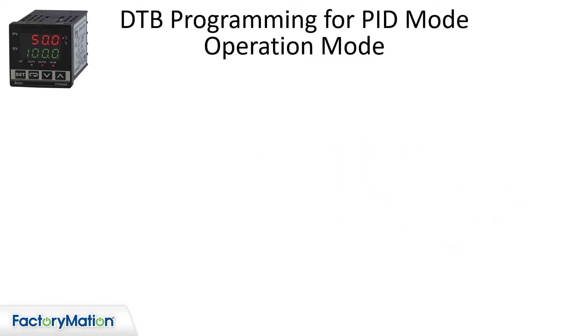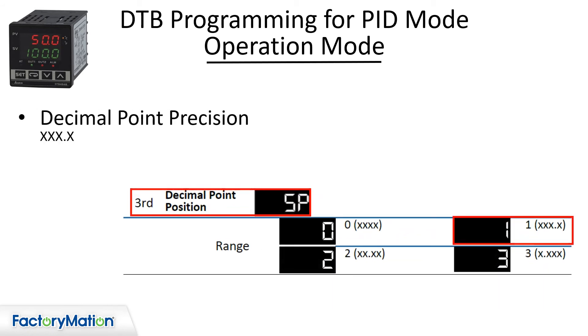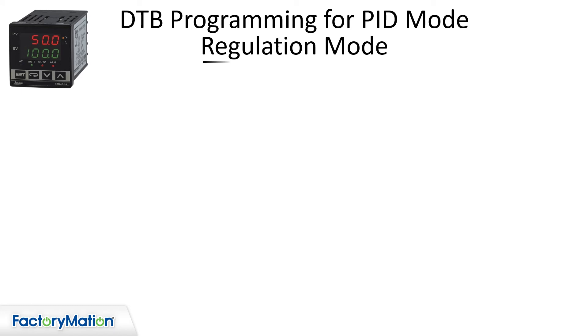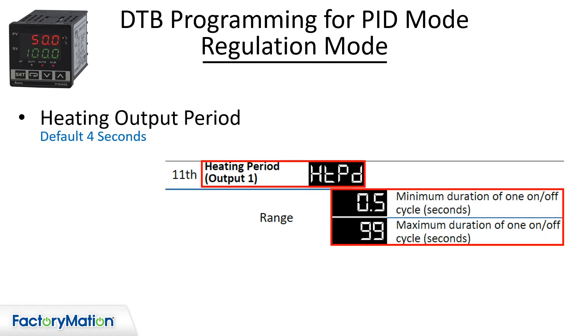Go to the operation mode. Set the decimal point precision to 1. Set the run stop mode to run. Go to the regulation mode. The heating period is set to 4 seconds by default — this is the length of time for the on-off cycle to the solid state relay.